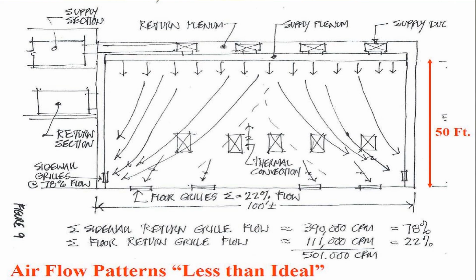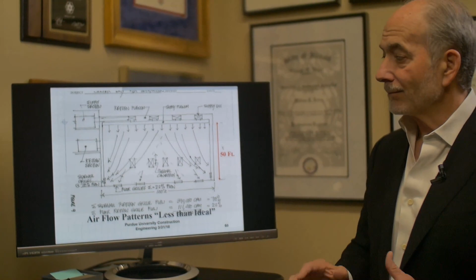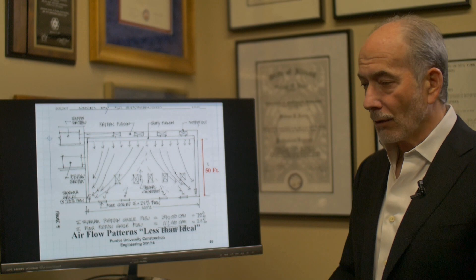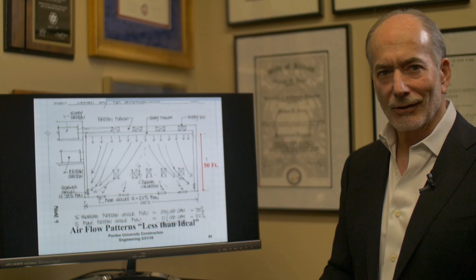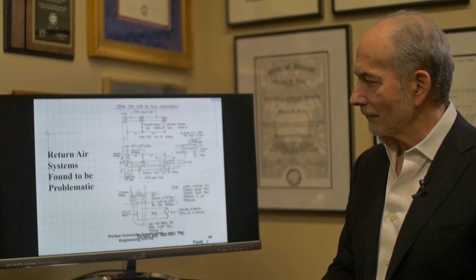We also evaluated the air distribution through the clean bays. This is a section through the clean bay. And this very simple diagram shows that the air parted in the center, creating a very low airflow in the middle, high airflow on the periphery, which is counterproductive to good temperature and humidity control. So for a variety of reasons, this facility was destined not to work properly, and unfortunately I wasn't called in prior to construction, but during construction. We did make some changes that did improve it. However, again, in that pay me now, pay me later, it would have been much simpler to fix it on paper than it would be to fix it after the fact.